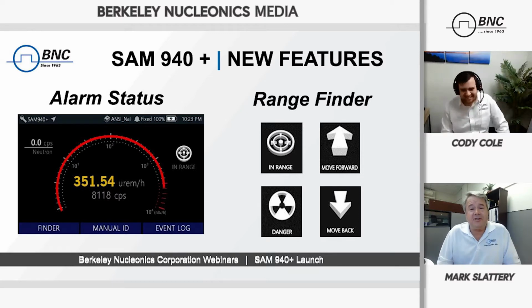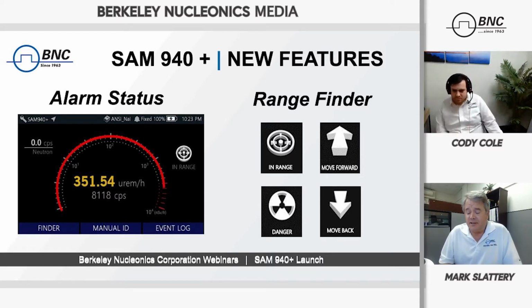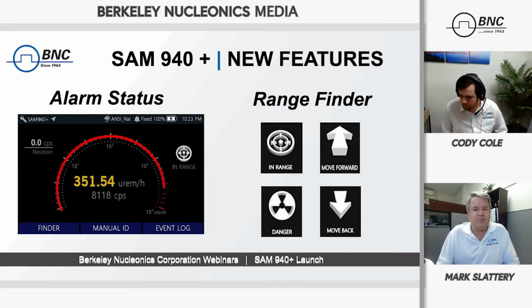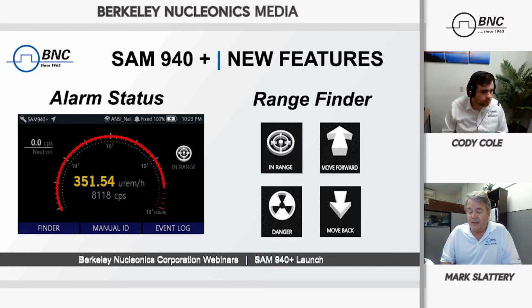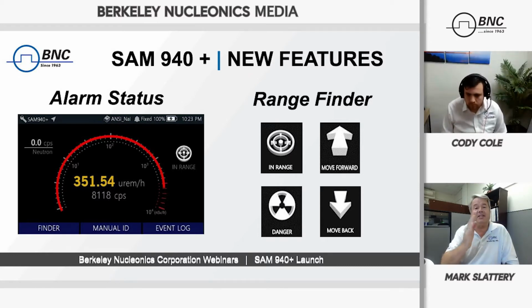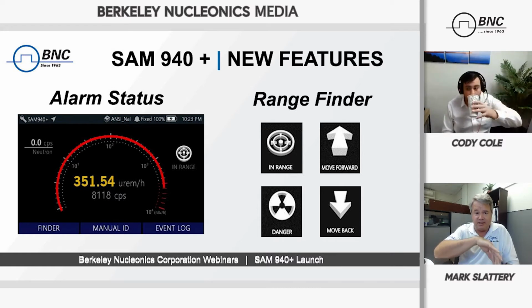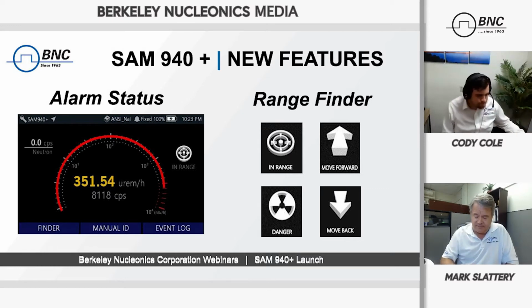One of the first things that you'll notice, particularly from the SAM 940, is that an important number was the dose rate. Another important number was the counts per second. And this used to be confined to a fairly small area in the upper right corner of the SAM 940. It is front and center now with the 940 Plus. I'd say these are useful things to know. Instead of the speedometer, we now have a gauge that, when we're not in an alarm, is in a white highlight. If we get into an alarm, it will turn red.